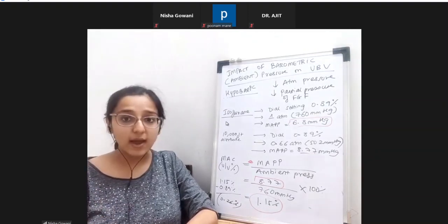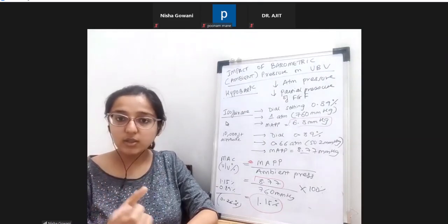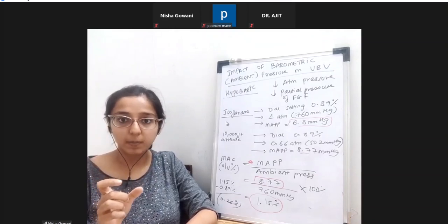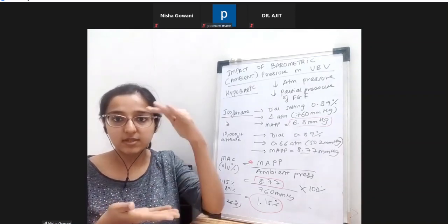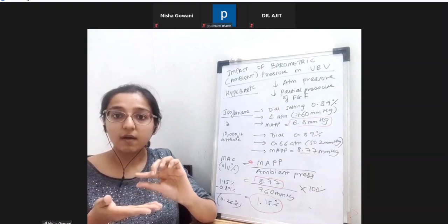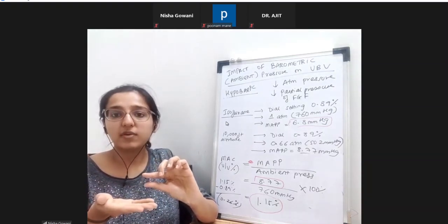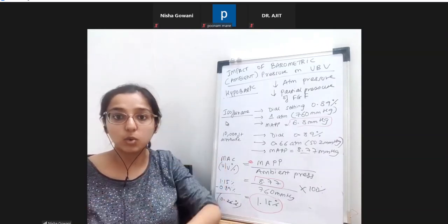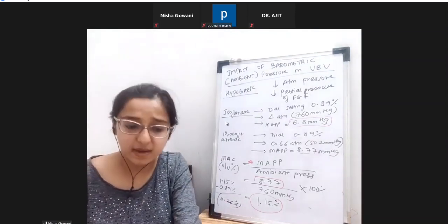As I showed you in the last diagram, how sevoflurane had it from the side, the filling port is kept lower down, very close to the vaporizing chamber, so that there is no chance of overfilling. If it were over here, there would be a higher risk of overfilling.